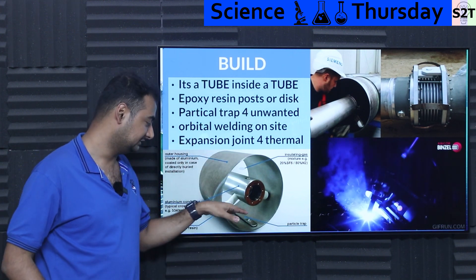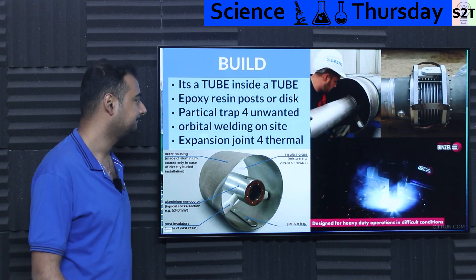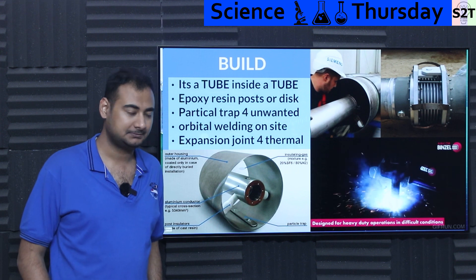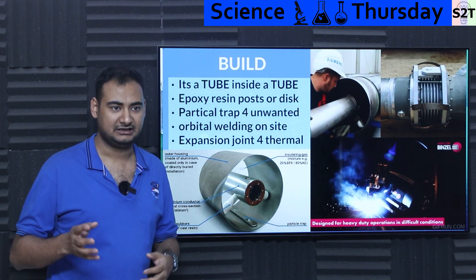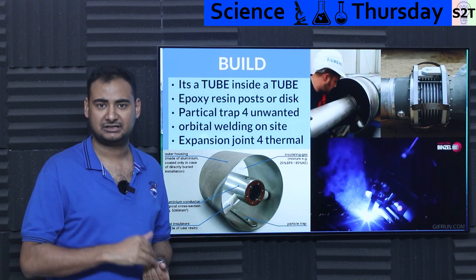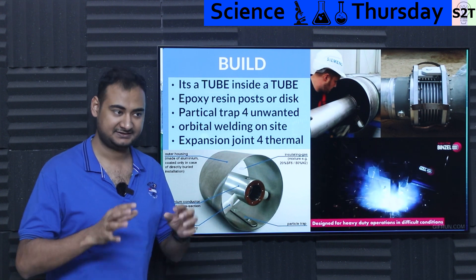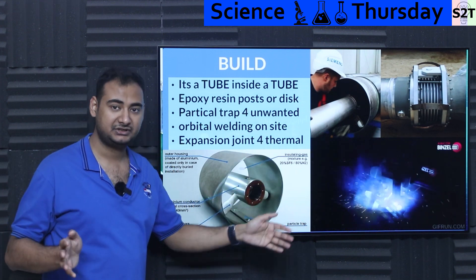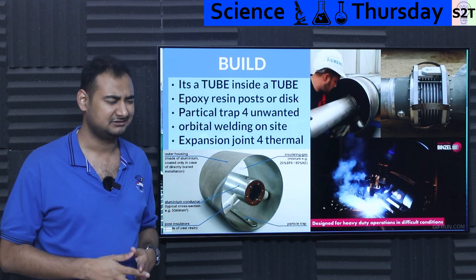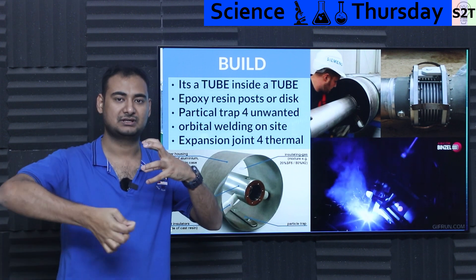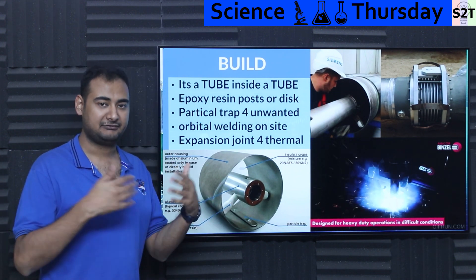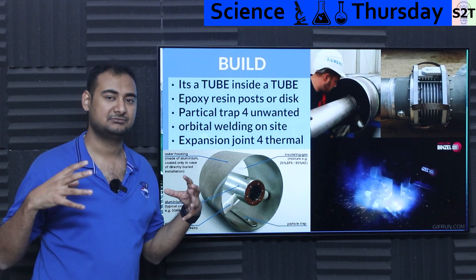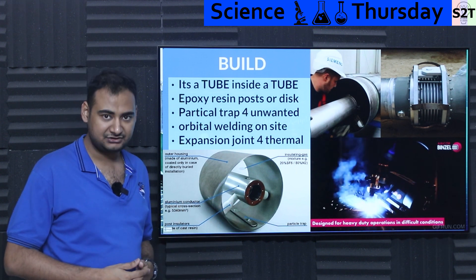There are particle traps on the bottom because things do evaporate under high electricity — they trap particles and stabilize the SF6 gas environment. They also perform orbital welding on site — these segments can't be spooled because the walls are thick to handle 5 to 7 bar pressure, similar to LPG or propane tanks. So they carry as large a segment as possible from the factory, then weld on site using orbital welders — a machine that goes around and welds it properly. After every five or six segments, there is an expansion joint made of corrugated sheet metal or silicone, allowing the system to expand and contract without fatigue while maintaining gas pressure.